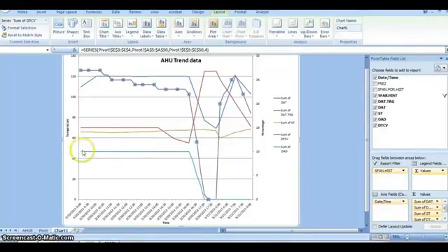And this blue line here, we know that the system's ventilating when it should be. It's about 12% open, which is minimum standards. And it kicks off as occupancy starts to decrease, which is great. In this purple line here, we have the control valve, which seems to be modulating down as temperature tends to go up. And that's a pretty steady temperature line.